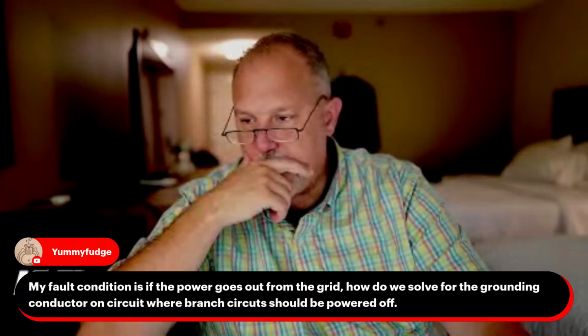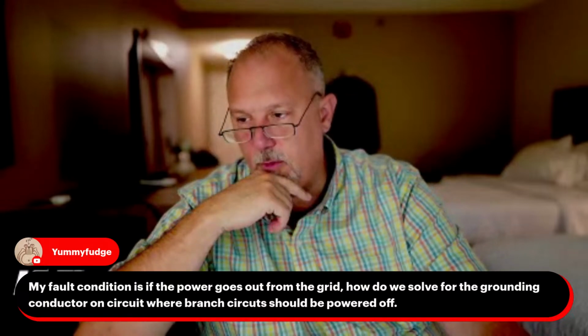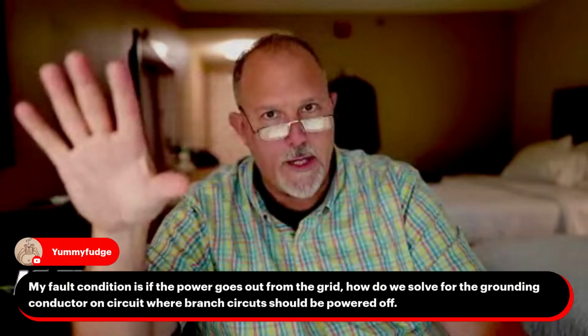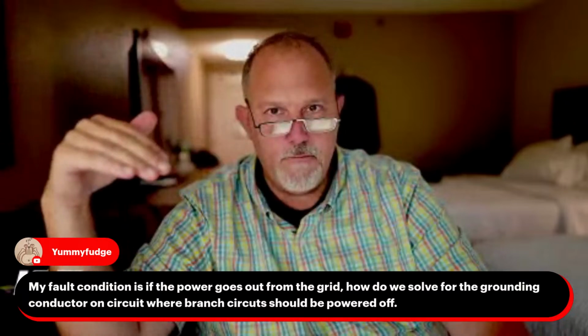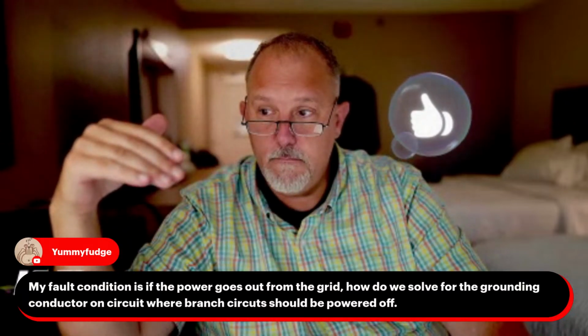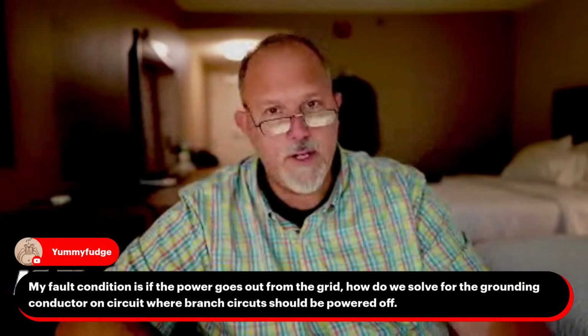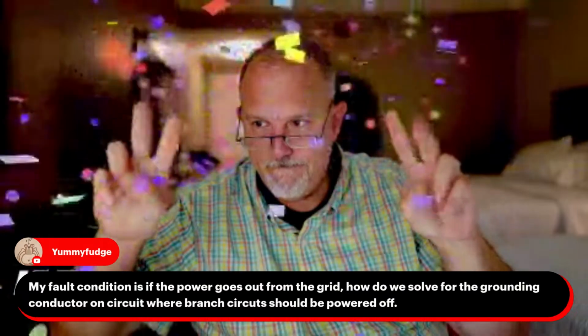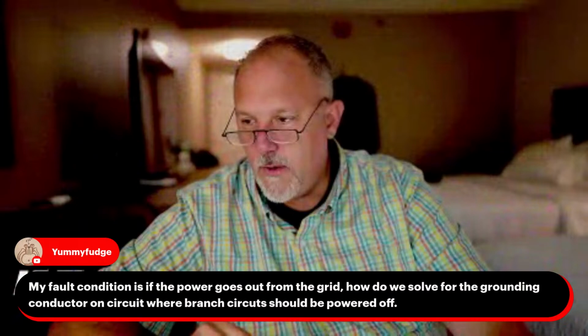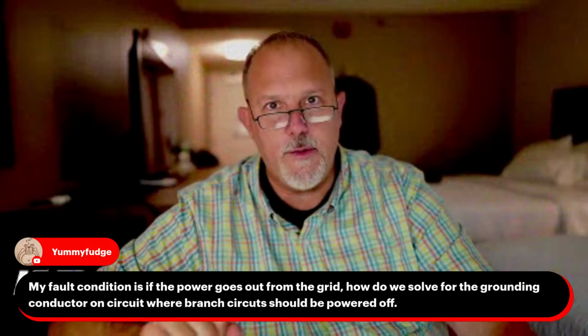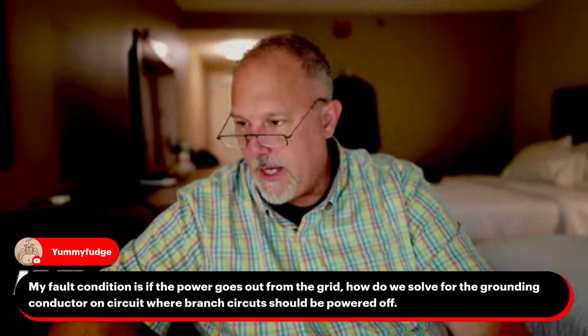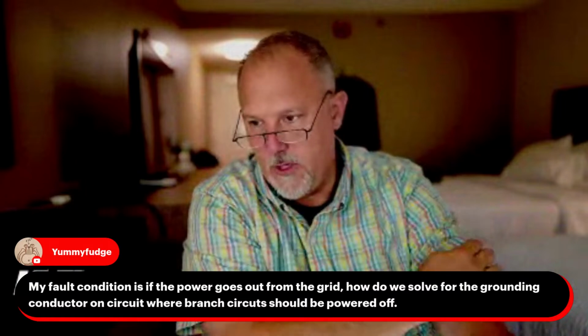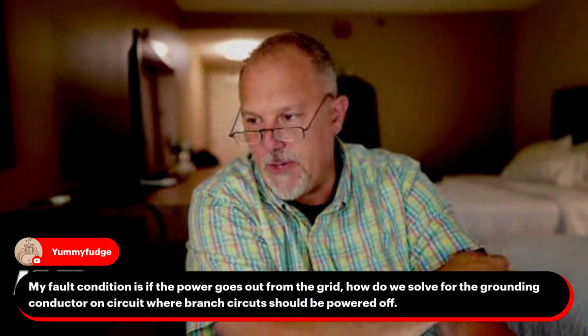Condition is if the power goes out from the grid. How do we solve for the grounding conductor on circuit where branch, I'm looking at Yummy Fudge's comment. Condition is if the power goes out from the grid. So if the power goes out from the grid, let's talk about that real quick. Utility interactive inverters shut down. Well, look at that. I got the thumbs up. Watch this. All right. So if the power goes out from the grid, a utility interactive shuts down. How do we solve for the grounding conductor on the circuit where the branch circuits should be powered off?